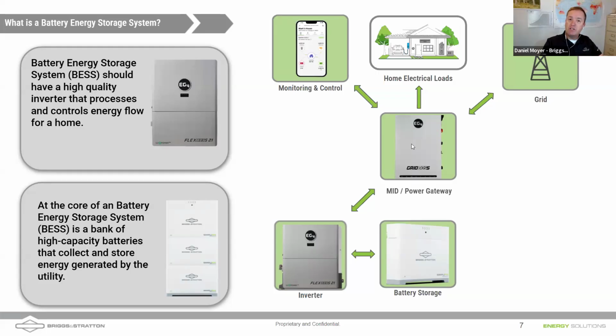What this allows us to do is decouple where the battery and battery inverter need to live from where the service entrance to the home is. Usually with hybrid inverters, you want to locate that hybrid inverter relatively close to the service entrance, so we're not running 200 amps of grid over to a hybrid inverter and then 200 amps right back out.